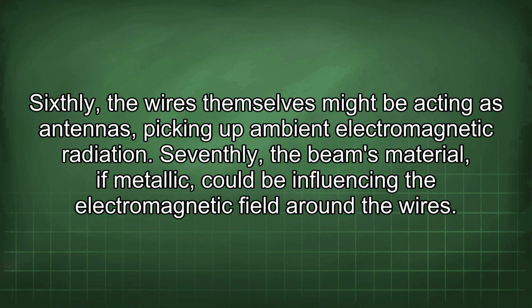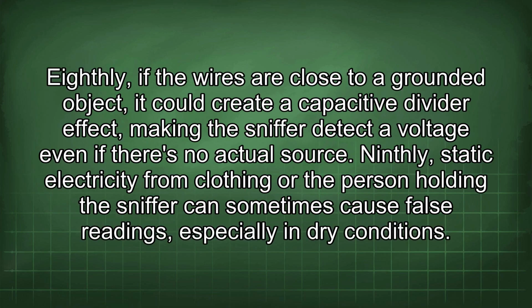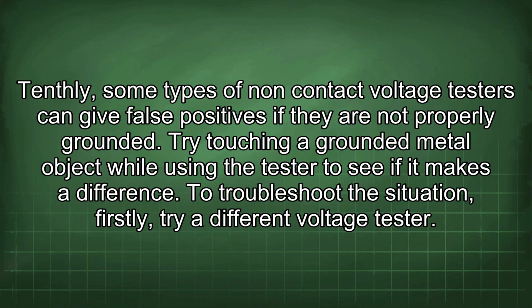Sixthly, the wires themselves might be acting as antennas, picking up ambient electromagnetic radiation. Seventhly, the beam's material, if metallic, could be influencing the electromagnetic field around the wires. Eighthly, if the wires are close to a grounded object, it could create a capacitive divider effect, making the sniffer detect a voltage even if there's no actual source. Ninthly, static electricity from clothing or the person holding the sniffer can sometimes cause false readings, especially in dry conditions. Tenthly, some types of non-contact voltage testers can give false positives if they are not properly grounded. Try touching a grounded metal object while using the tester to see if it makes a difference.